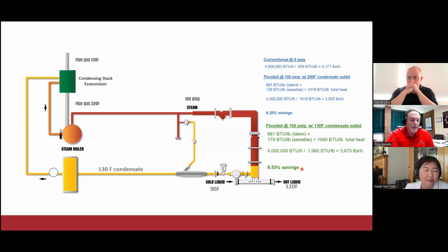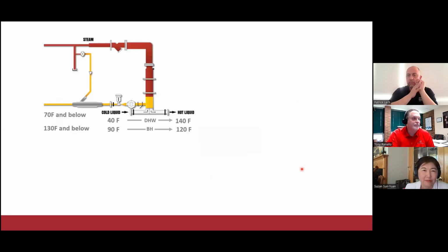But let's take a look at another scenario where we can add a condensing stack economizer. Once we have low temperature condensate coming back to the deaerator or to the steam boiler, we can now condense the flue gas, and we can look at 95% overall efficiency of your steam plant. We'll get to that in more detail in a second here.